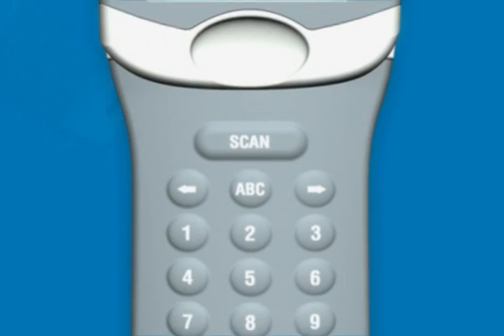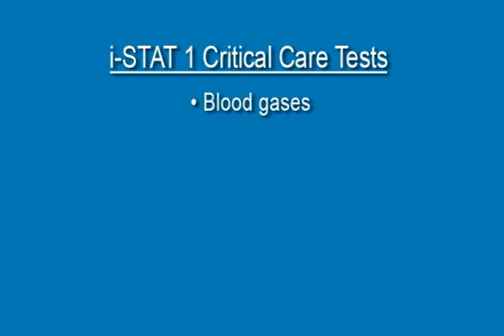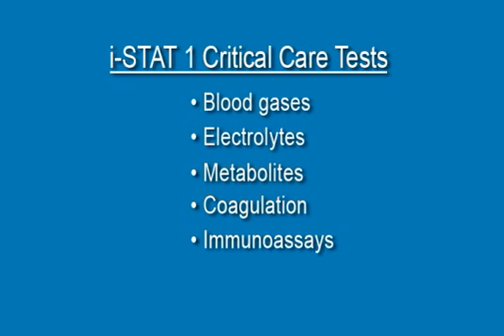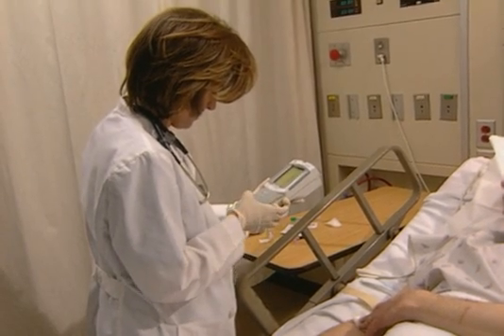The i-STAT 1 Handheld Analyzer is a true point-of-care device for critical care tests that include blood gases, electrolytes, metabolites, coagulation, and immunoassays, as well as glucose. It is designed to be used at the patient's bedside by healthcare professionals trained to use the system.